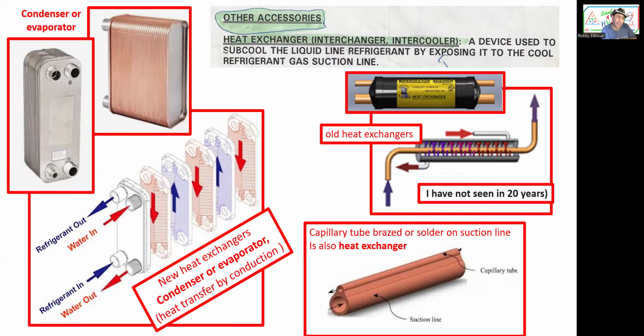This is the old style heat exchanger. It's pretty much the suction line and liquid line going around it. I haven't seen that in 20 years. I don't think it's needed anymore. The whole purpose was to make sure the liquid line and suction line don't sweat too much. But I guess now we have better installations. I don't see it much anymore for some reason. It's not needed anymore, the old heat exchanger, pipe in a pipe.